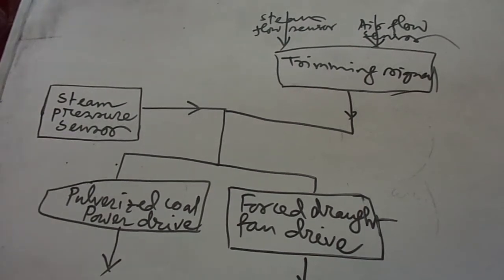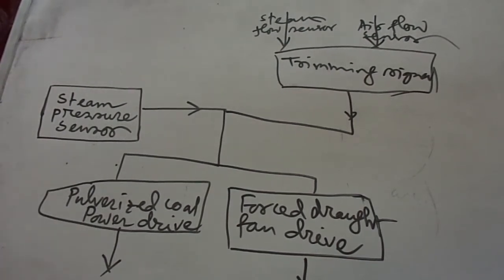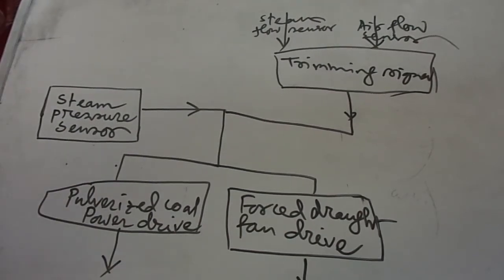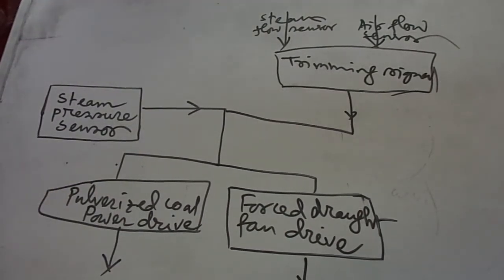Since it is often difficult to obtain accurate fuel flow, a steam flow sensor is sometimes substituted for the fuel flow sensor. Usually about a 5-second delay is allowed when changing coal flow and air flow, to prevent a momentary rich mixture with high fuel air ratio and thus assure smoke free combustion.